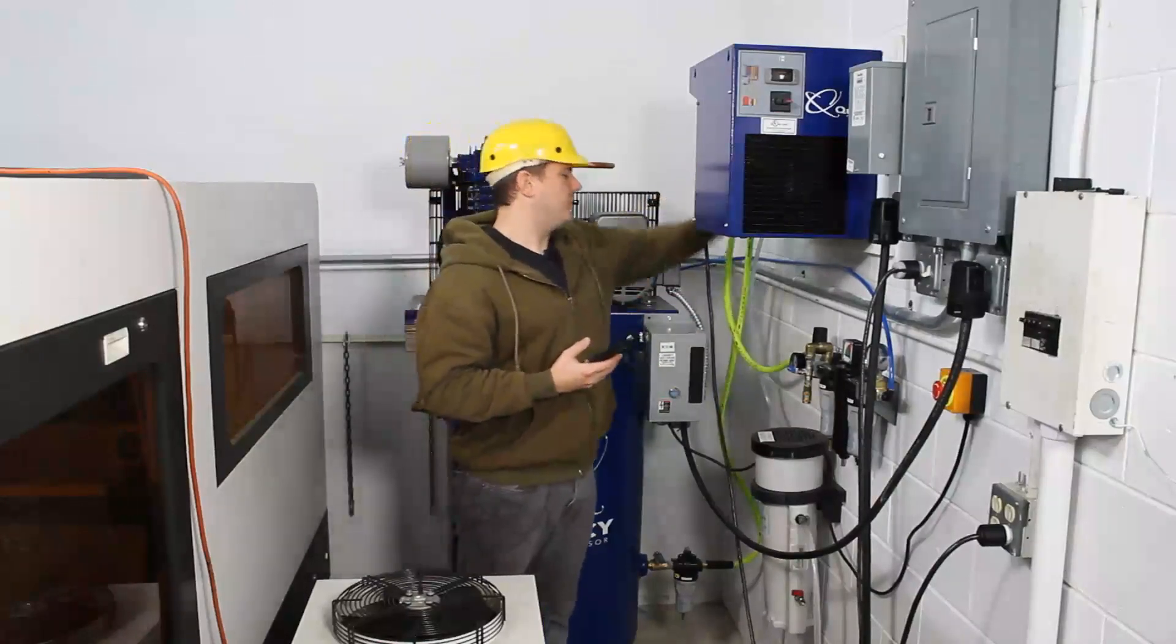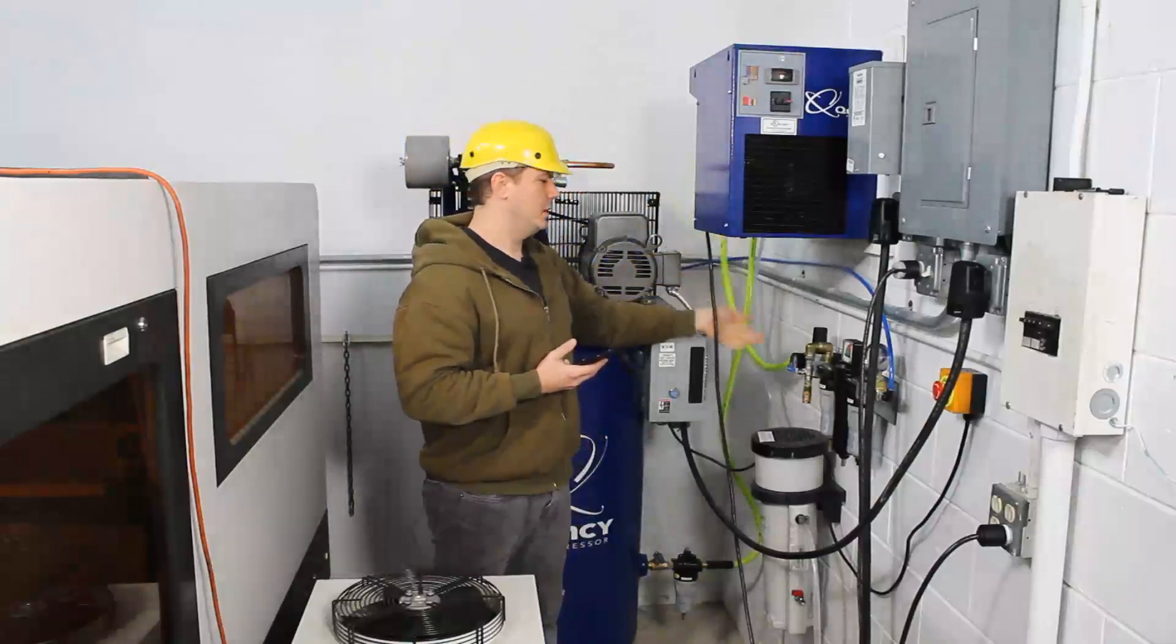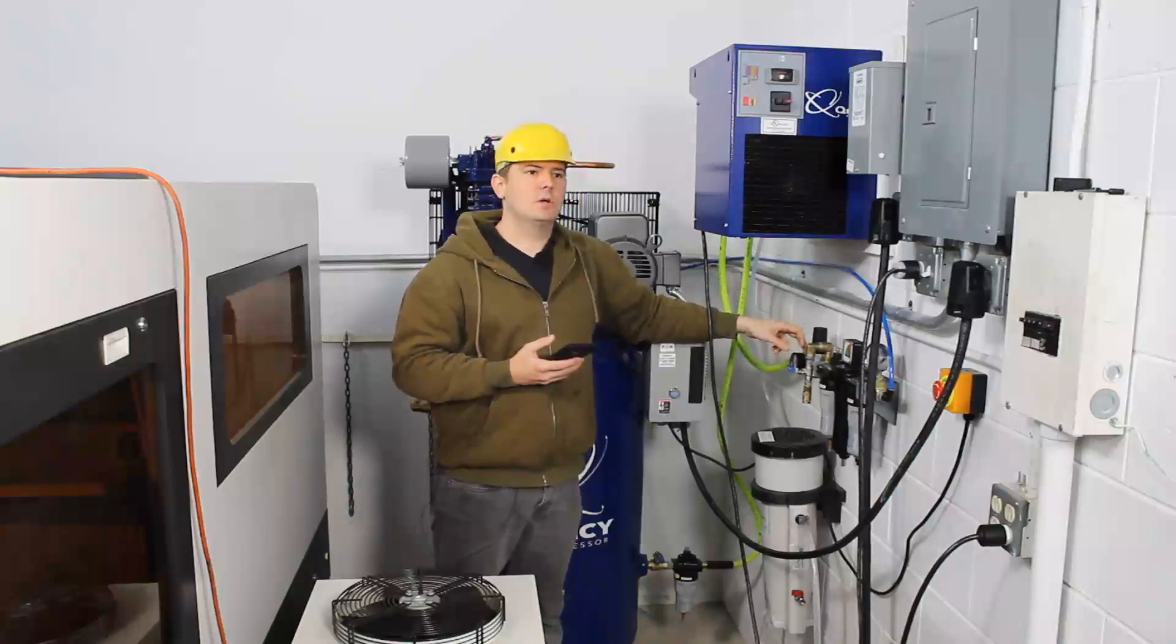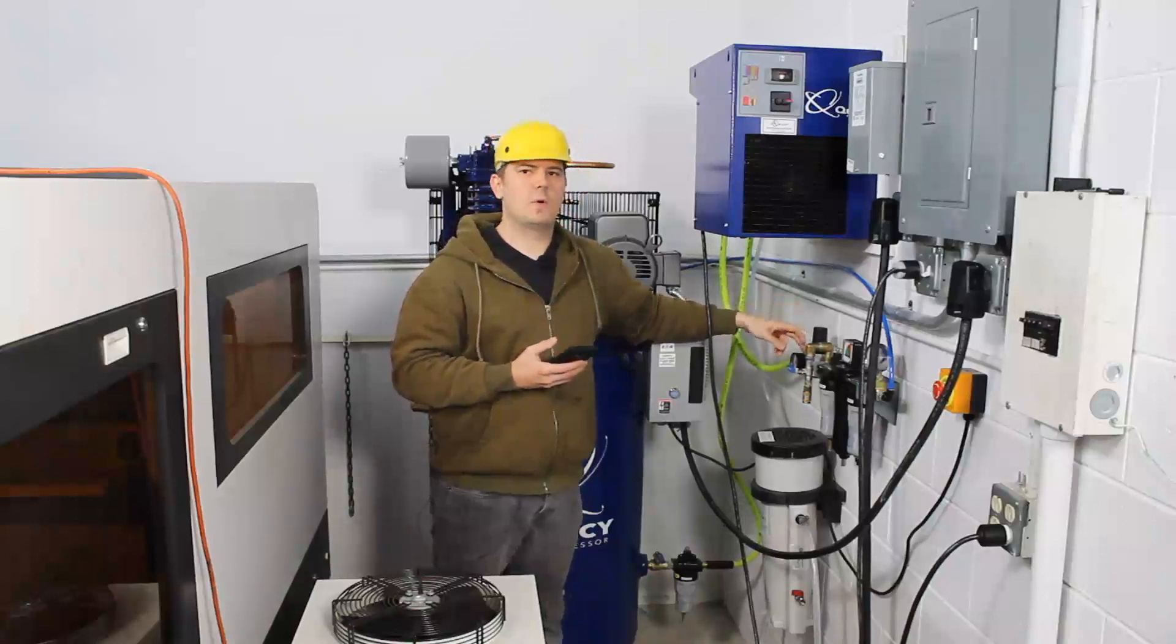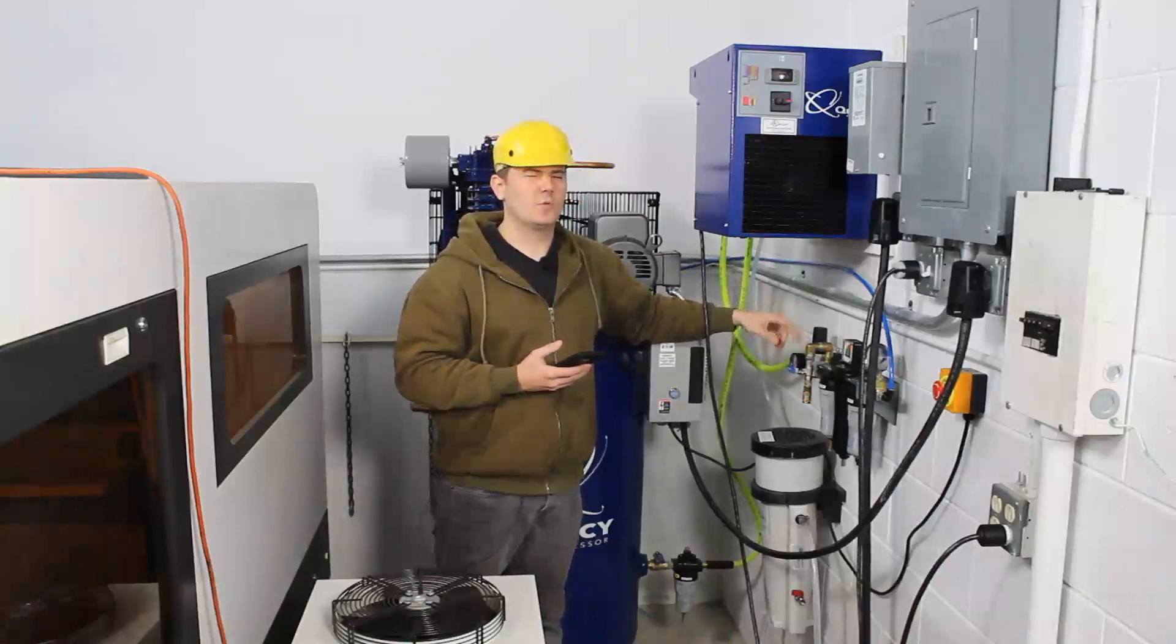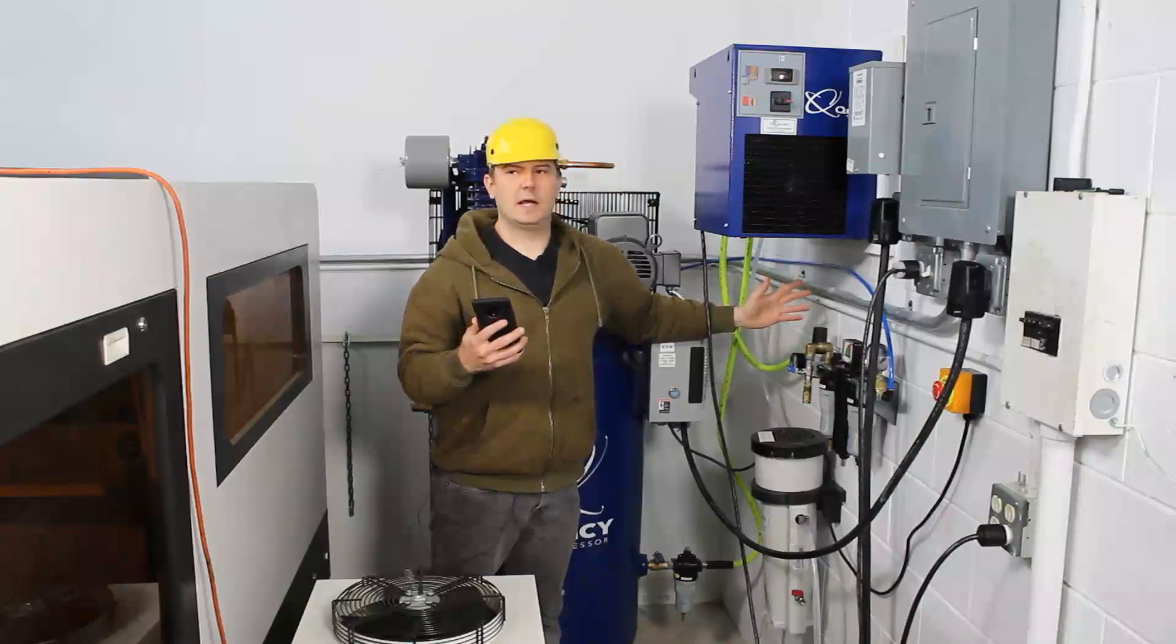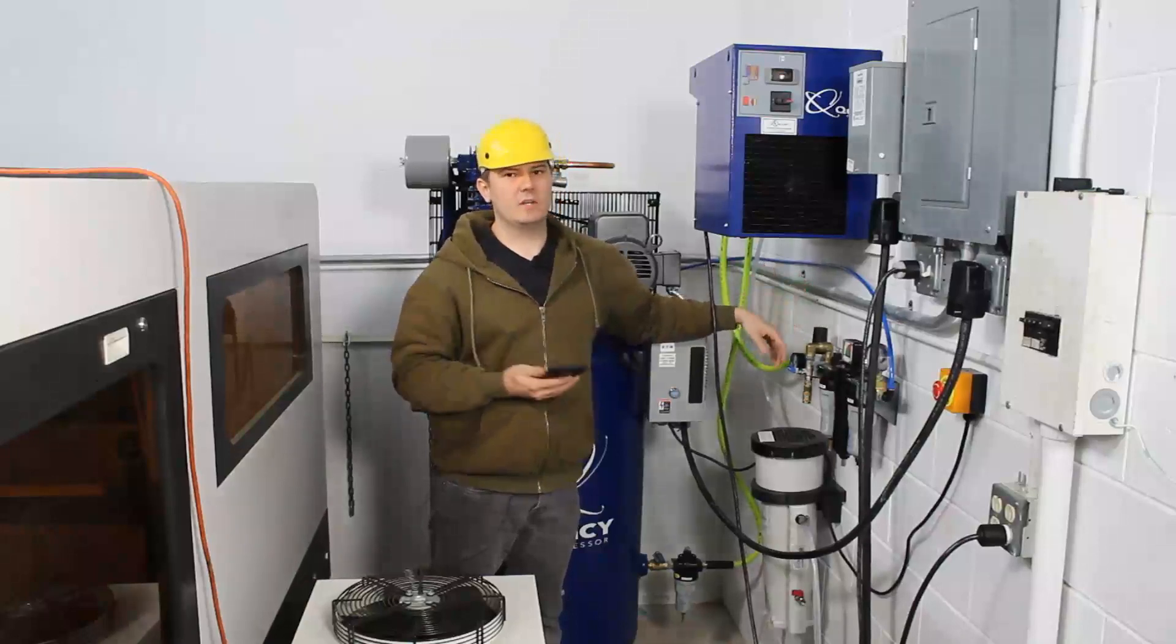We go on to another flex hose. Again, this doesn't need to have a swivel. Ours did. It male fittings into a regulator. Make sure on your regulator that it not only can handle the input pressure, but also output pressure. Our first one we purchased, it could take 225 PSI in, but it maxed out at 140 and that was kind of a useless regulator.